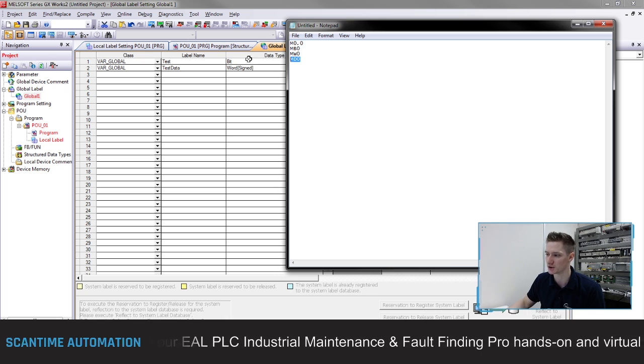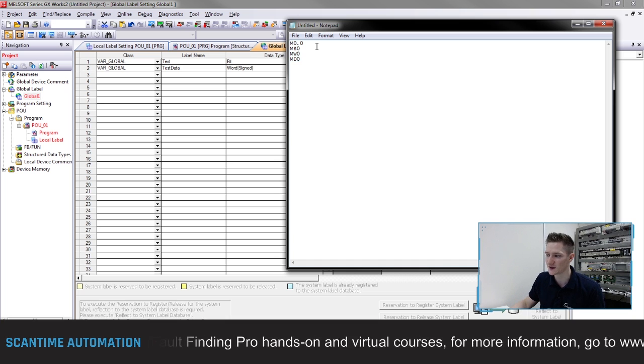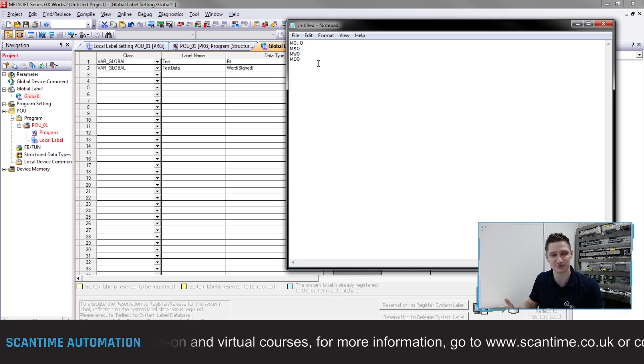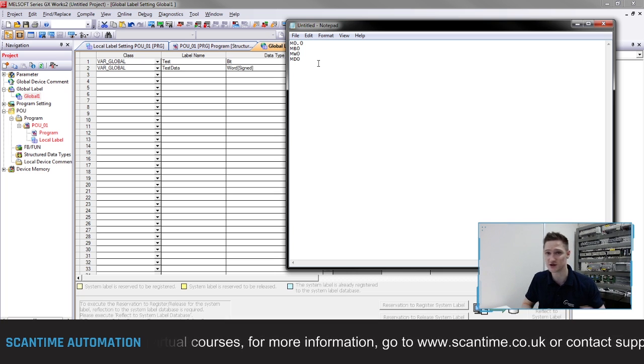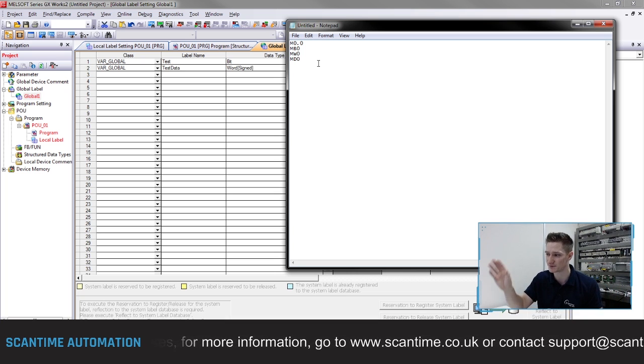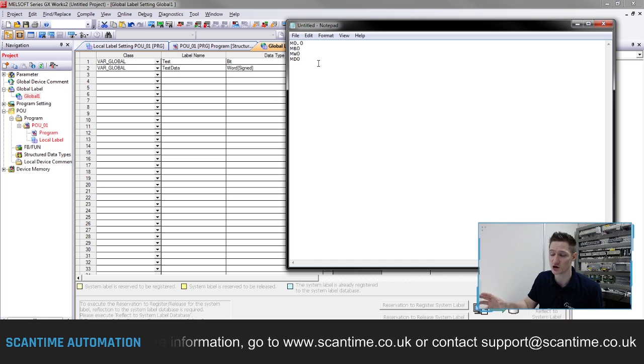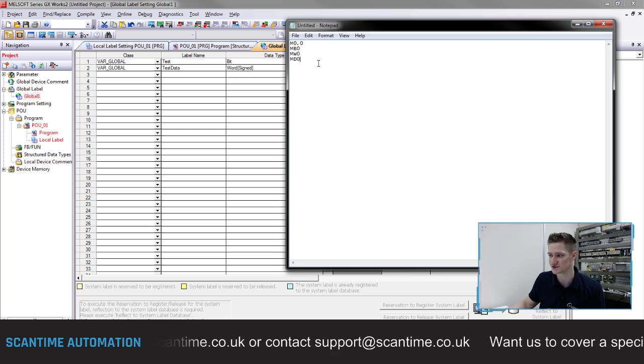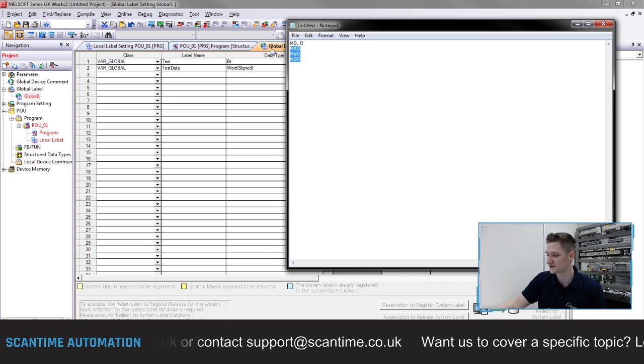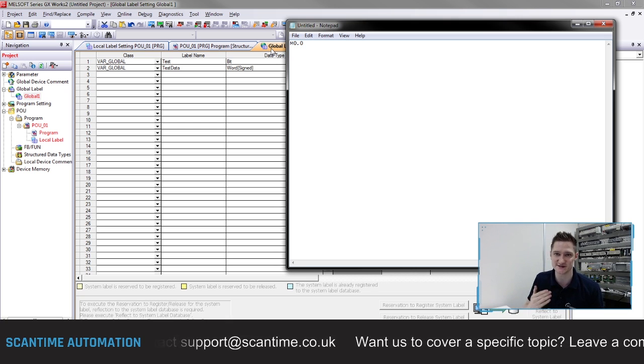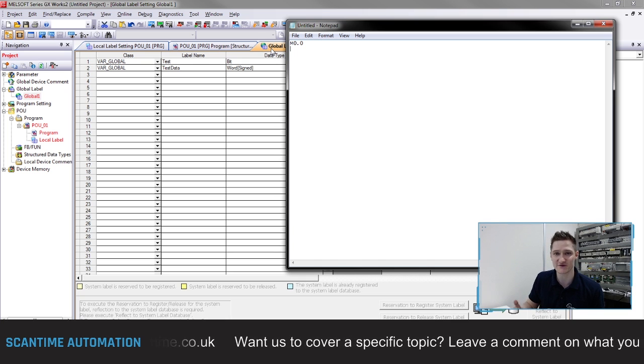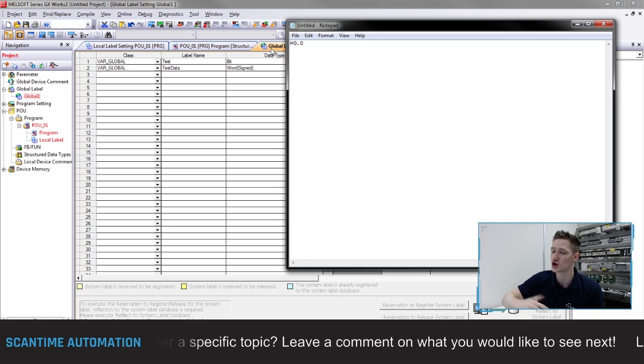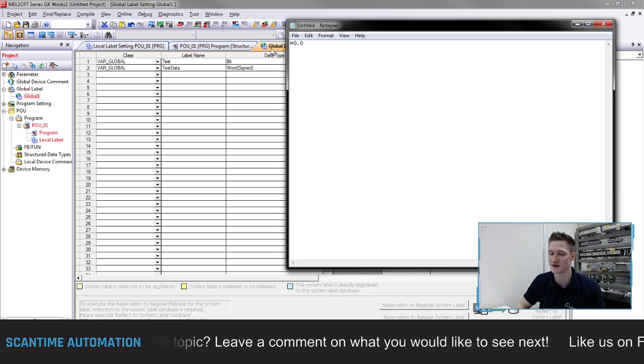The problem is I have overwritten address zero multiple times. Inside the program I'm using it as a bit, as a byte, a word, and a double word - and inside of Siemens you can't do that, as you're overwriting the bits with these other registers. Inside of Mitsubishi it's fine - you can use M0 and D0 and they are completely separate. But inside of Siemens you can't mix these around. A bit is either going to be a zero or a one - a digital signal that just turns on and off.